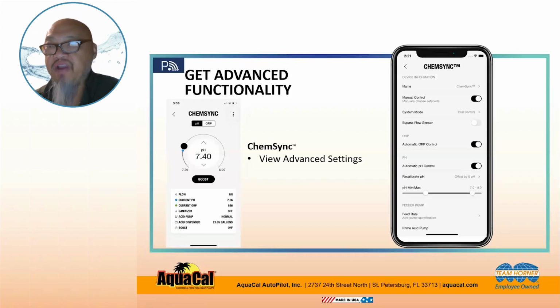One of the things that I would recommend in regards to this setting is that when you prime the acid pump, when you first start up a system, use water only, okay? The reason why I say use water only is because if you put an acid water solution in there and you discover that you've got some leaks or you need to loosen up a fitting, you're going to have acidic water going through there. So rather than dealing with acidic water, maybe burning your hands or damaging some concrete that it may drip out on, if you use just water only, you don't have any fear of any kind of damage at that point.